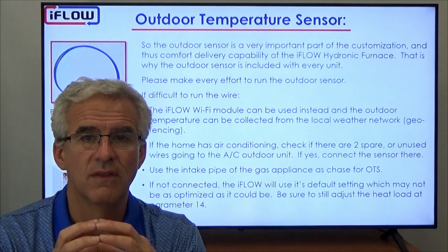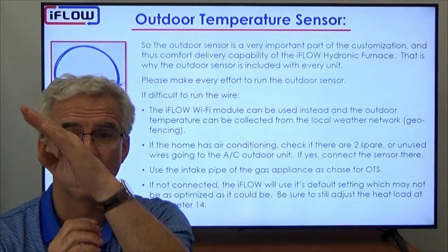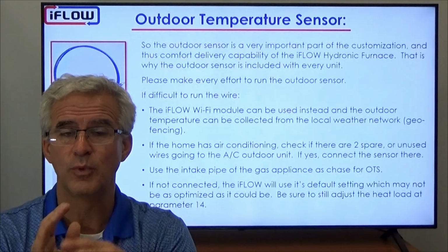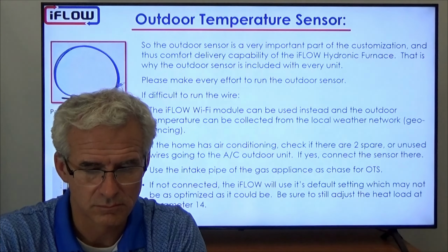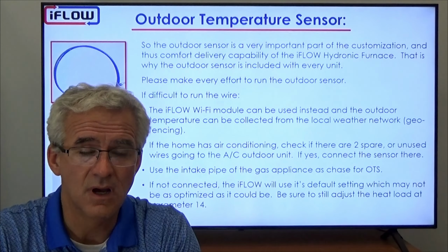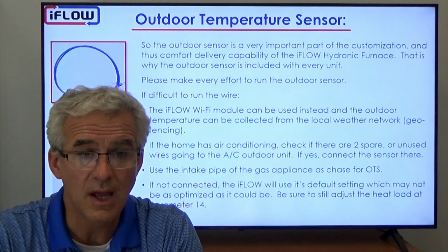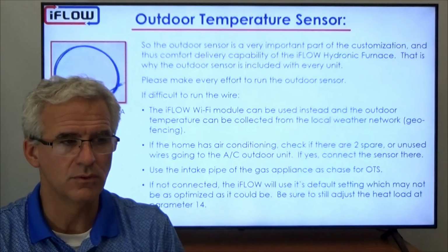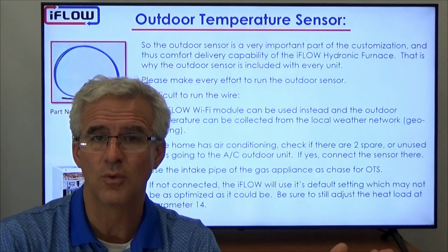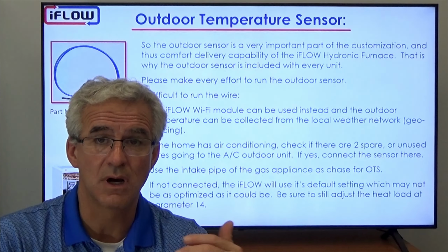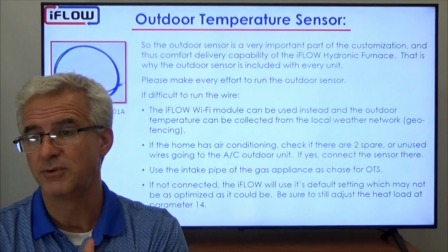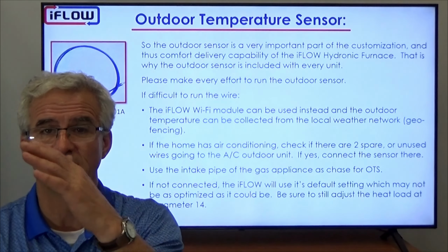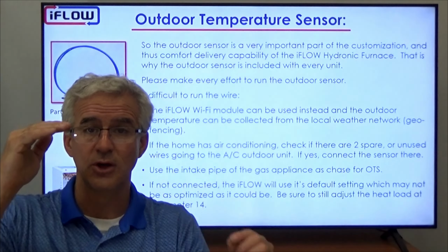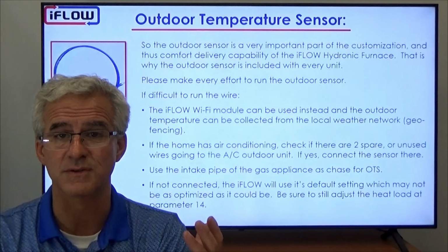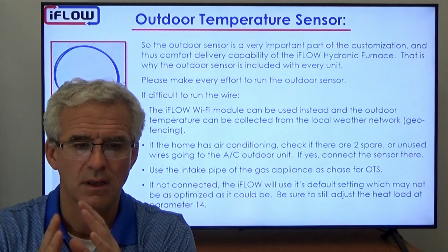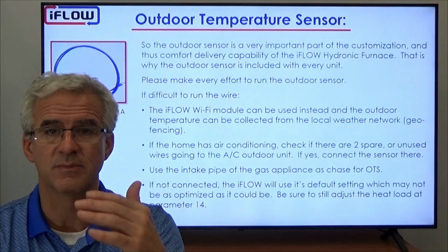And it's the outdoor sensor that will allow us to do that, because it gives us the temperature, it creates the slope, and based on that slope, we deliver the BTUs into the house. If it's not connected, then unfortunately it won't have a target to reach. So you can adjust the parameters all you want, but it doesn't know what it is outside, so it doesn't have a reference point. So it's always going to be operating at what you've set it to. For example, if you set parameter 14 to 50,000, it knows it has to deliver 50,000, but it doesn't know where on that slope you are at any point in time, so it'll run at 50,000 BTUs. It's going to modulate based on the return air temperature, but it's not going to give you the ideal slope and ideal customization that you could get.